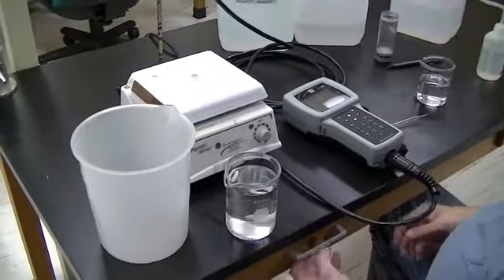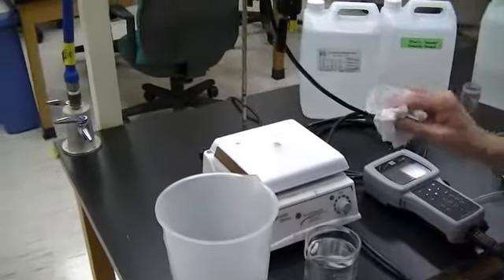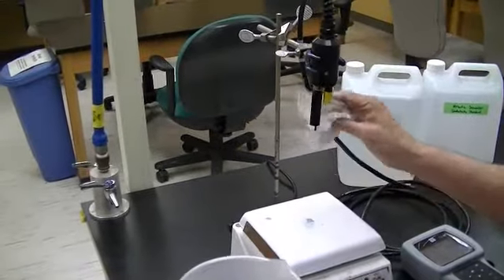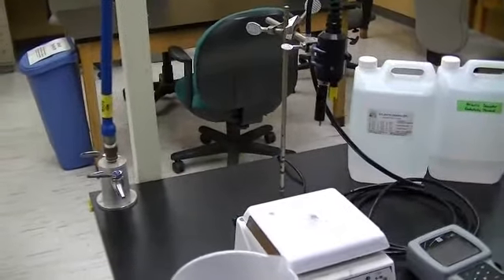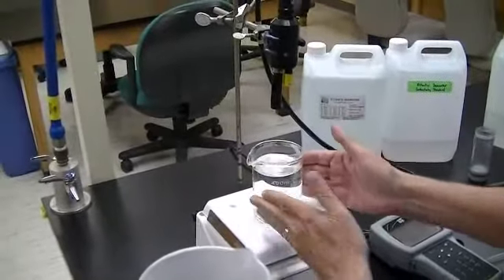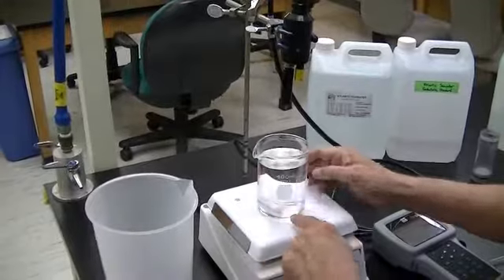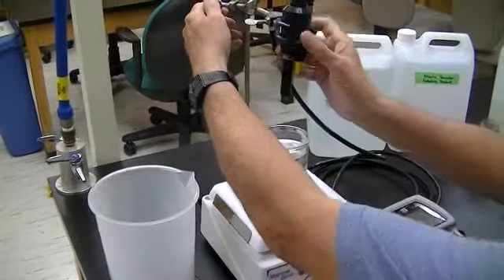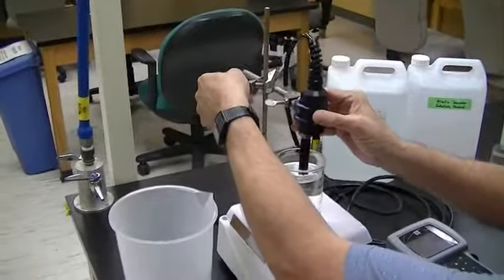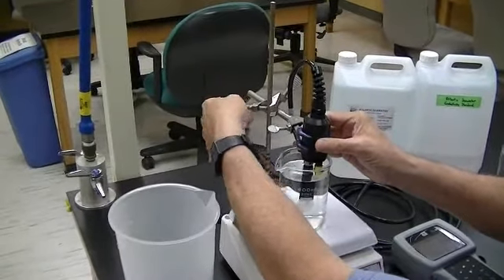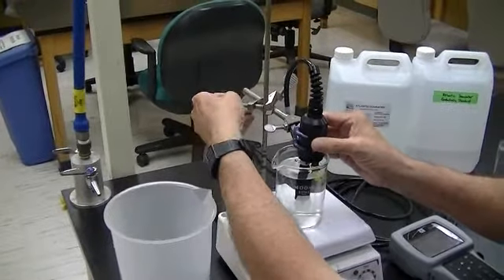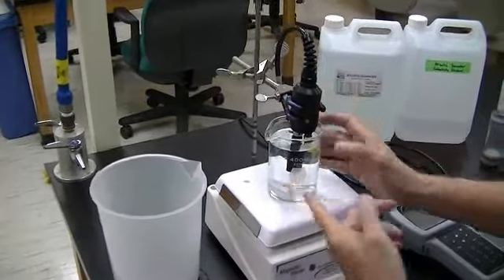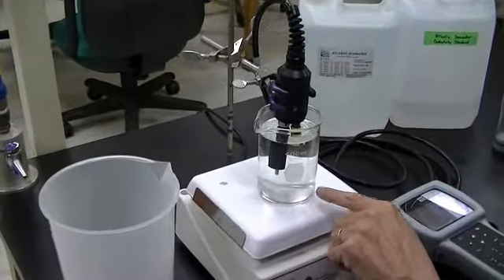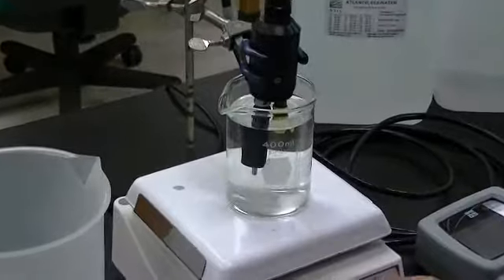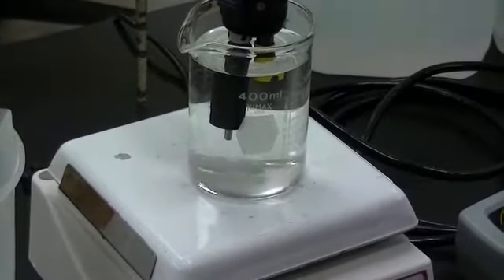Okay, now it's not a bad idea to take your paper towel or something and just blot the main big drops off of this, and then you just take your natural seawater from the boat basin with a spin bar in it, and you lower the whole thing down until you're immersing that black probe and the yellow probe, and make sure the hole in the side of the black probe is under the surface, but also make sure that the probe isn't hitting the spin bar. Then you turn the spin bar on just a little bit, just like that, and watch the display.